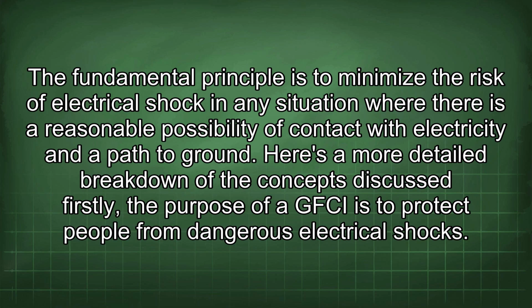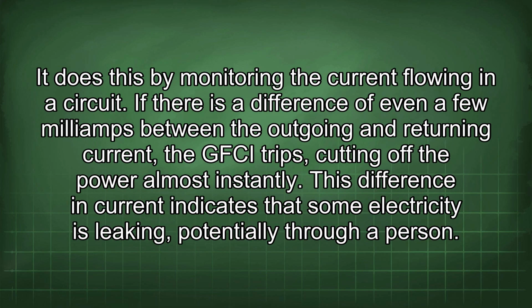Here's a more detailed breakdown of the concepts discussed. Firstly, the purpose of a GFCI is to protect people from dangerous electrical shocks. It does this by monitoring the current flowing in a circuit. If there is a difference of even a few milliamps between the outgoing and returning current, the GFCI trips, cutting off the power almost instantly. This difference in current indicates that some electricity is leaking, potentially through a person.